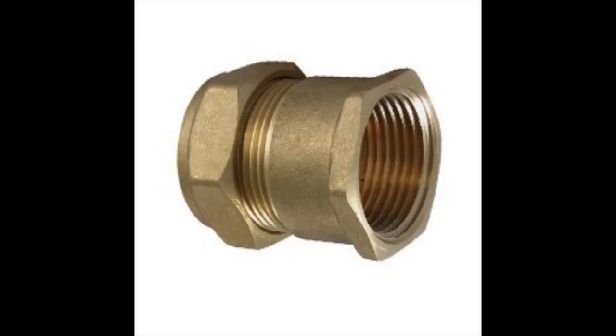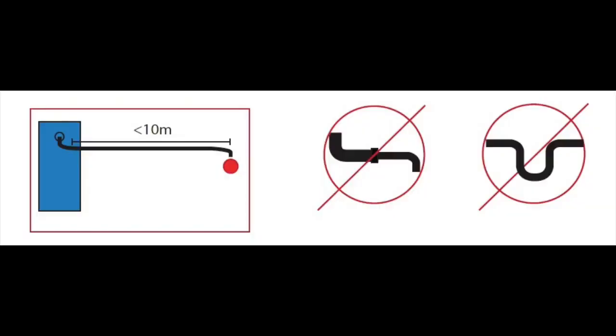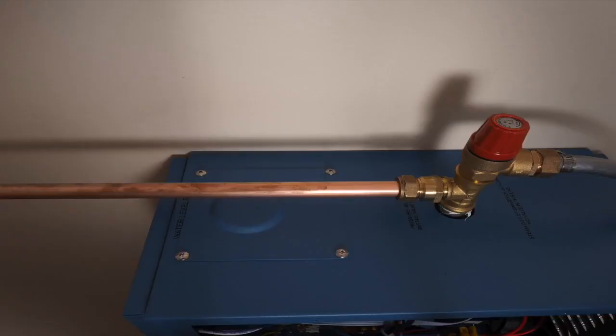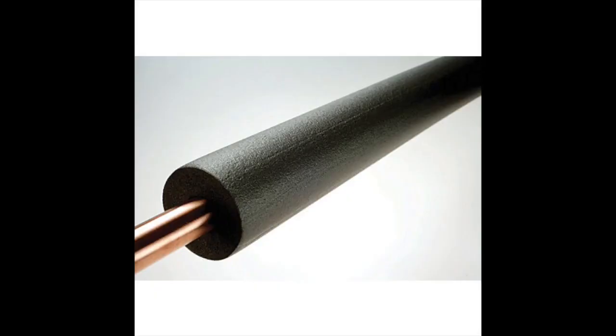Sizes eight kilowatts and above all come as three quarter inch. The steam pipe must not go down and then up as this will create a trap which will block the steam from getting through. Do not run the steam pipe over the water probe access plate. Make sure you insulate any unconcealed pipe work or for increased performance insulate the pipe work. This will stop any spluttering of condensed water coming out of the steam nozzle into the room.